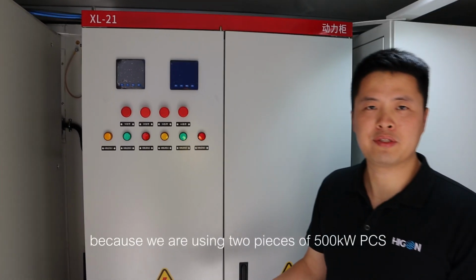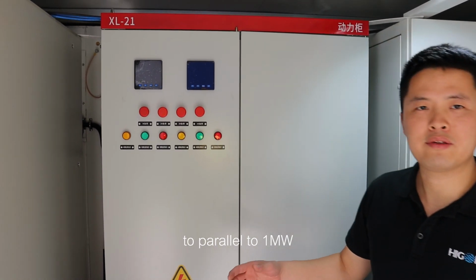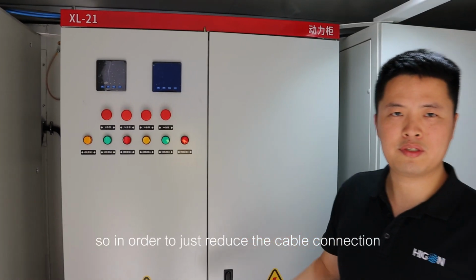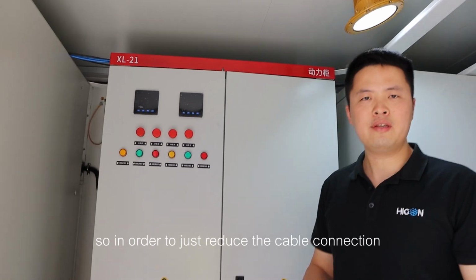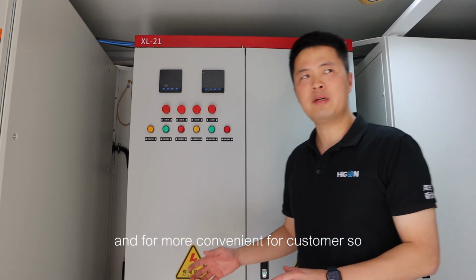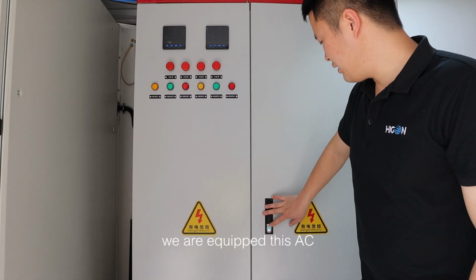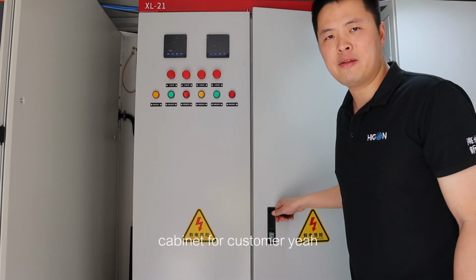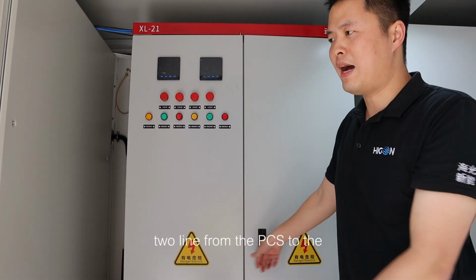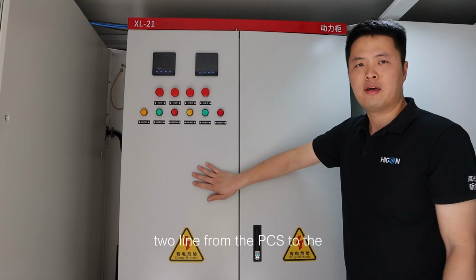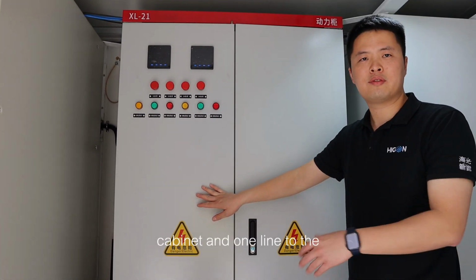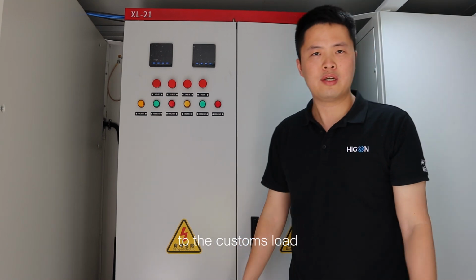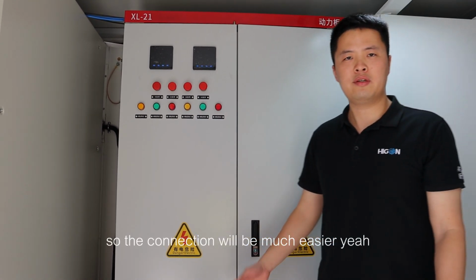Because we are using two 500 kilowatt inverters in parallel to make 1 megawatt, in order to reduce the cable connection and be more convenient for the customer, we equipped this AC cabinet. So 2 lines go from the PCS to the cabinet, and 1 line to the customer's load, so the connection will be much easier.